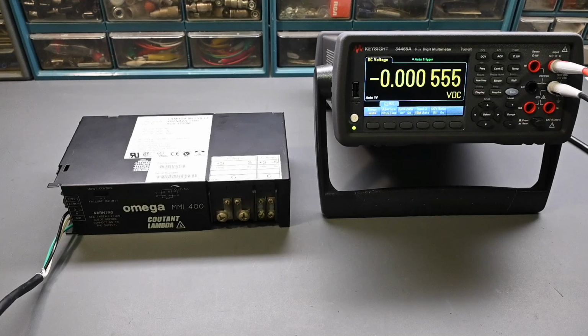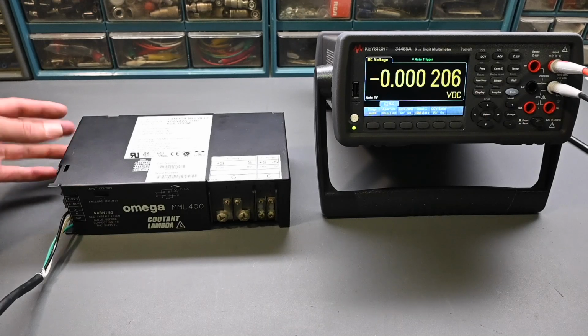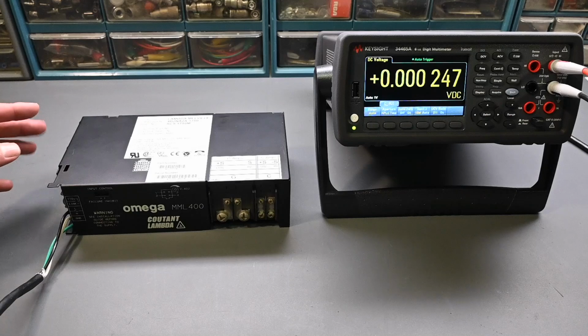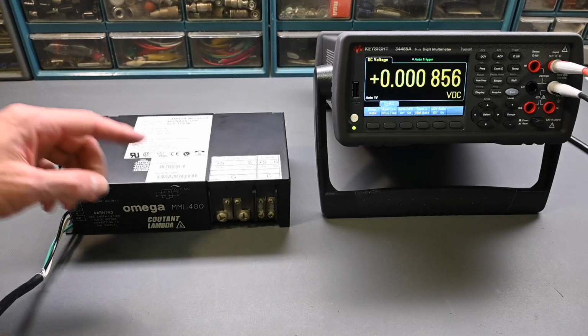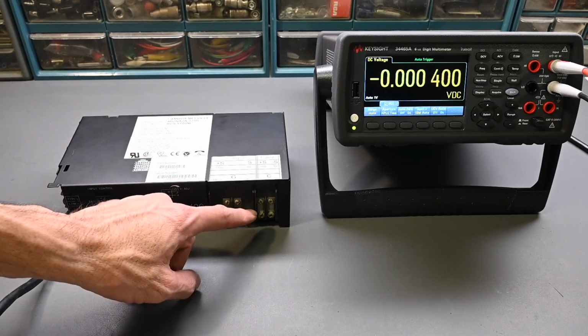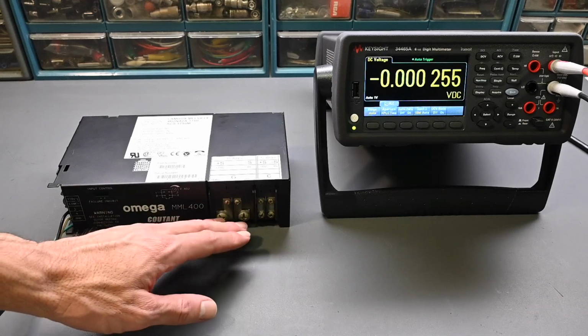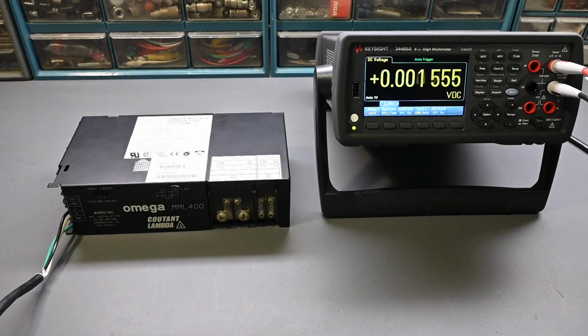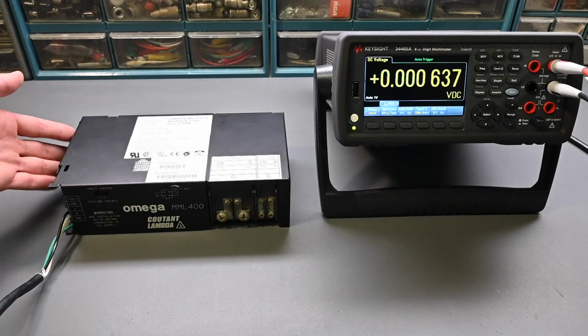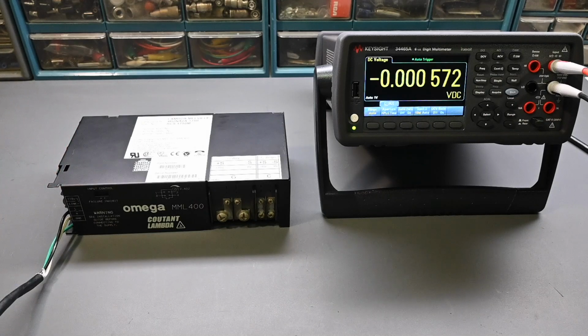And what I notice is that when it's not operating correctly, this cooling fan is kind of stuttering and rocking back and forth. But I don't think there's anything wrong with the fan motor, because at the same time the voltage on the output terminals is very unstable and it's very low. It's not within the normal operating range. So I think the motor just doesn't have enough voltage to operate correctly.